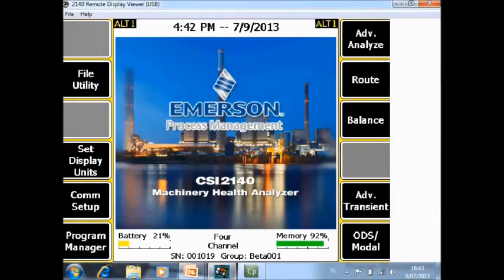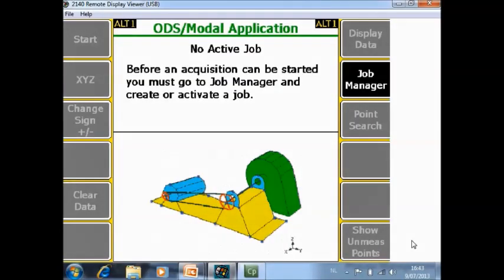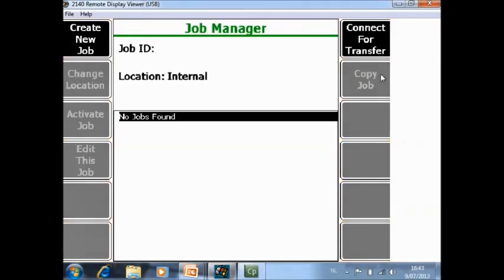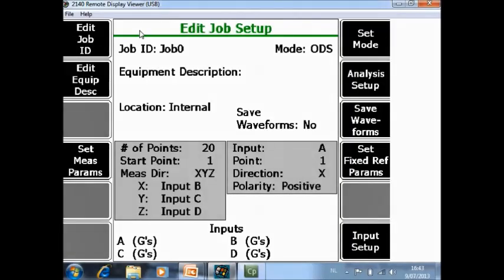What you are seeing now in front of you is a home screen of the CSI 2140 Machinery Health Analyzer. If you want to start an ODS or modal job go to F12 ODS modal and the first thing that we have to do is to create a job. So F8 Job Management and I will create a new job. So now there is a job created with the name Job0.